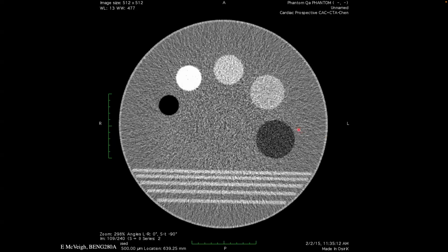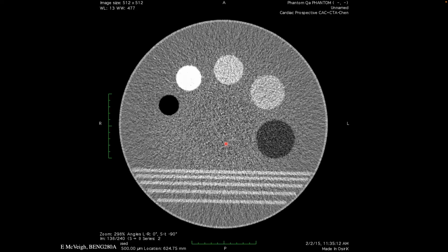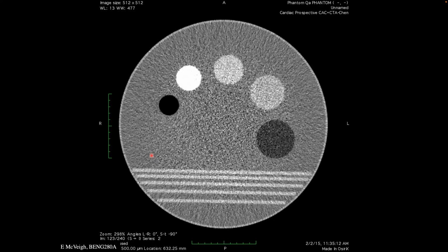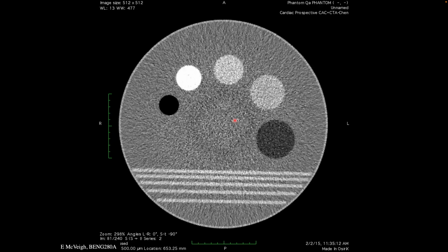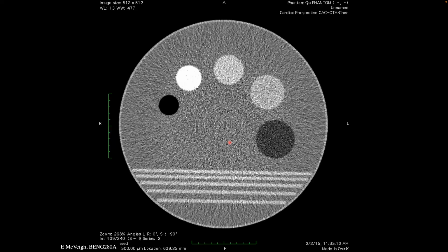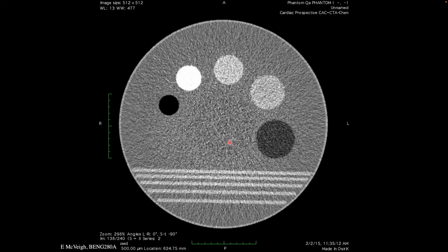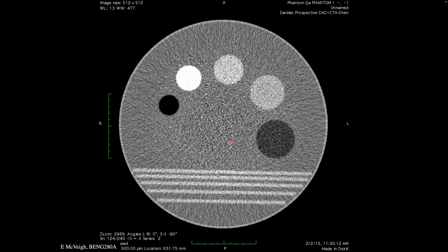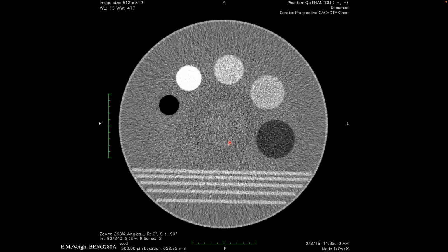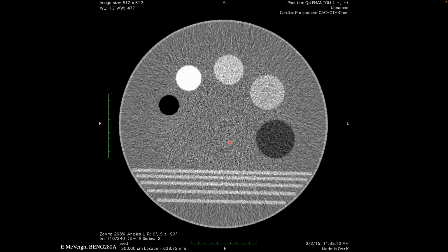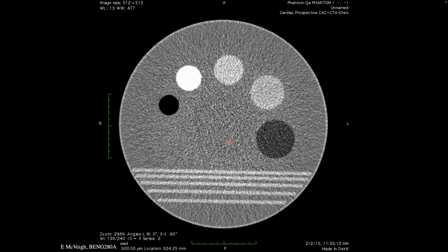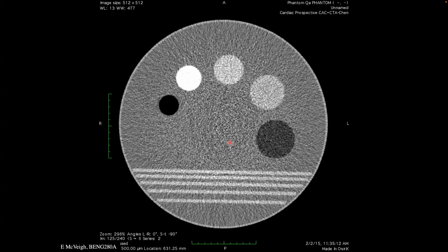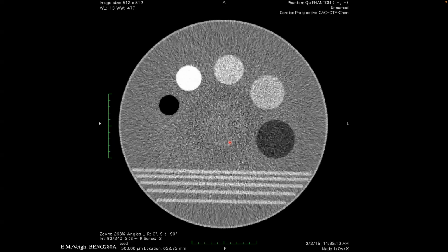Okay. So the same question gets asked again. Why is the noise level higher in the central part of the image than, say, in the outer part of the image? The simplest explanation would be that in the center part of the image, less interpolation needs to be done to the data in order to make the reconstruction. Without that interpolation, the noise passes through, whereas with the interpolation to create the pixel values out here, the noise gets smoothed more.